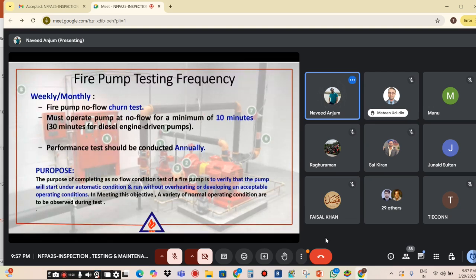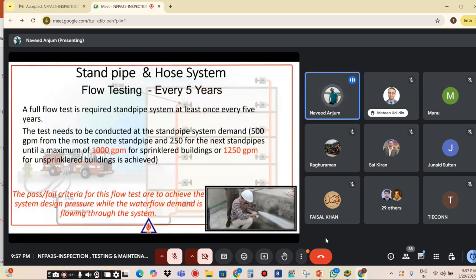The purpose of completing a no-flow condition test of a fire pump is to verify that the pump will start under automatic condition and run without overheating or developing unacceptable operating conditions. So we have to check our fire pump like this.